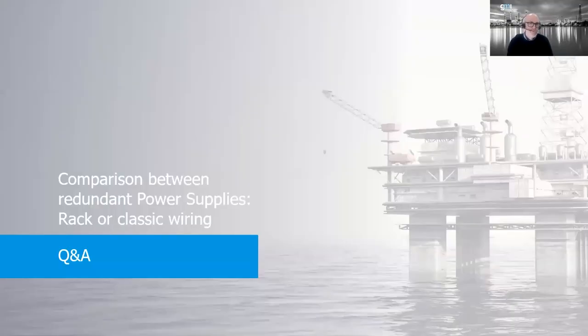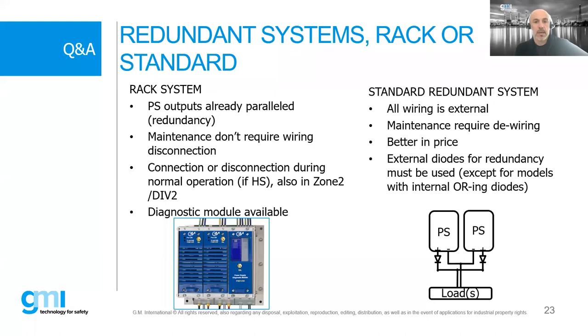Okay, Andrea, and which is the difference between the redundant power supply in a rack or with the classic wiring without the rack? Yeah, of course, in a standard redundant supply, the wiring is external, and maintenance requires rewiring. The solution is, of course, more competitive in price, but requires these external diodes that also consume a lot of energy, so it causes a voltage drop. There are some, let's say, disadvantages in using that. The rack is a little bit more expensive, but the output is already connected.